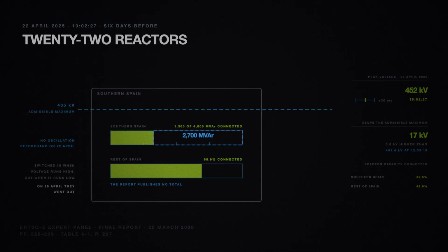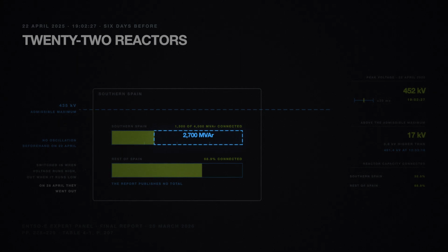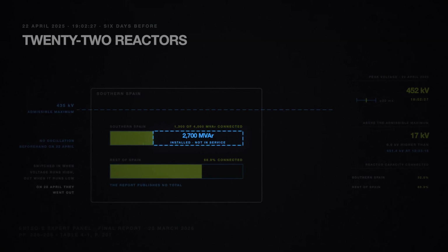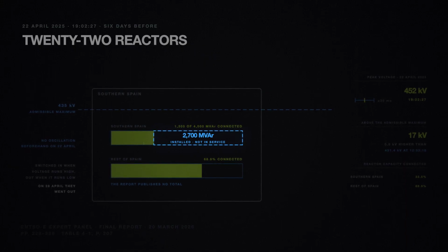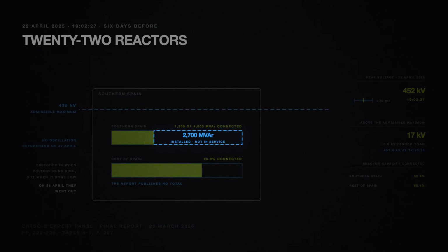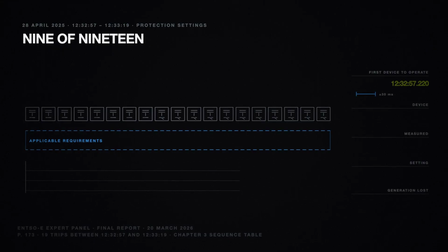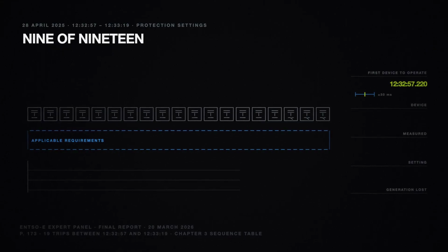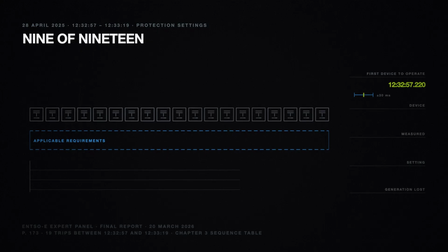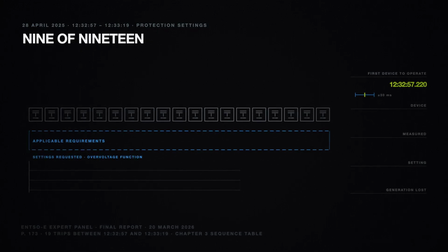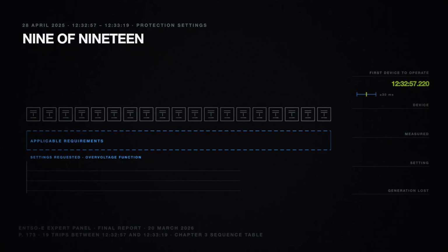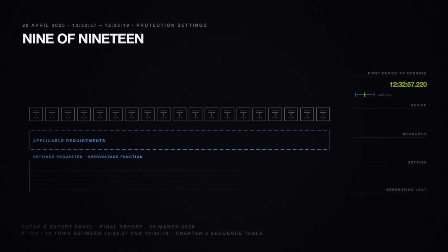2/3 of the absorption in the south of the country was installed and was not in service. That is the one hollow thing in this film that is hollow because of a switch position, rather than because nobody wrote the number down. 6 days earlier, 22 had been enough. Between 12:32 and 57 seconds and 12:33 and 19 seconds, 22 seconds, 19 protection devices operated. The panel asked for the settings behind them. Settings for the overvoltage function were received for 9 protection devices out of the 19 trips analyzed.